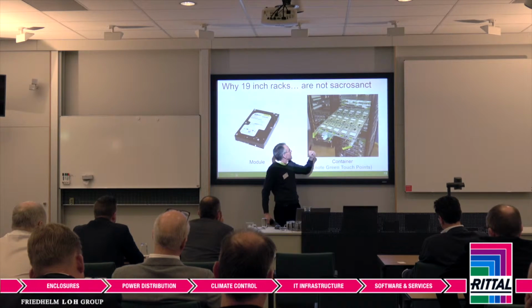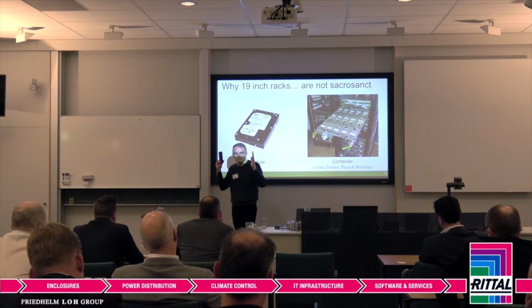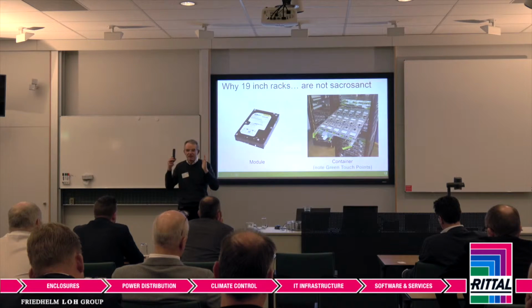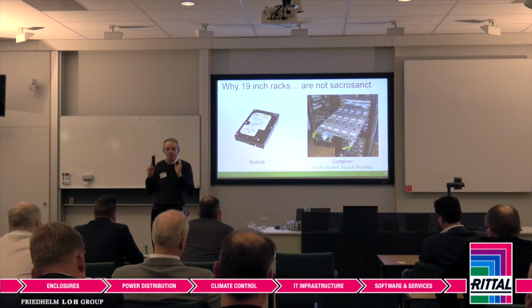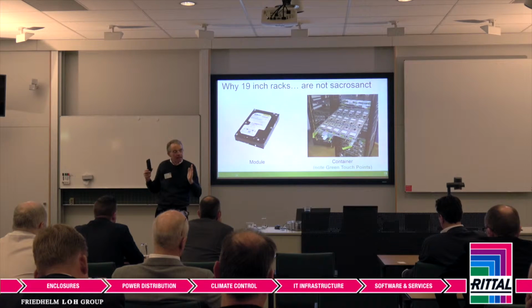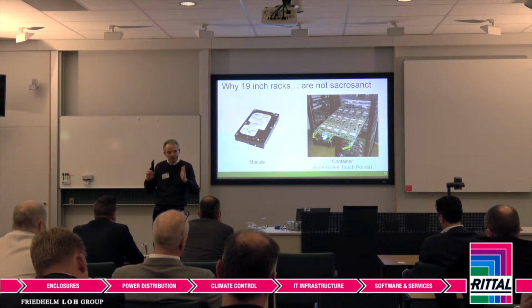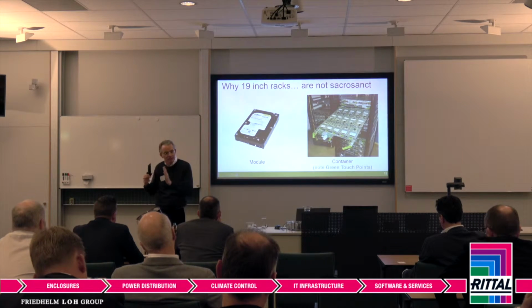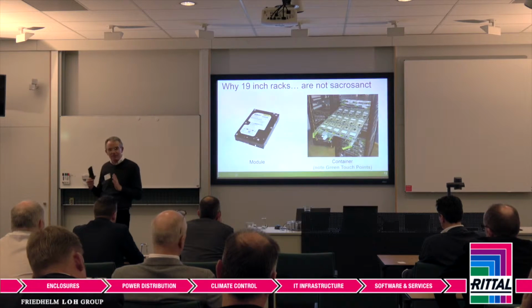So what the OCP rack does, it takes the vertical rail and widens it out slightly, so you can get 5 in. But the volume of the rack is no bigger. Consequently, you get 25% more hard drives in the rack, which is a benefit on space, but it's also a disadvantage on weight, because that is a very heavy rack.